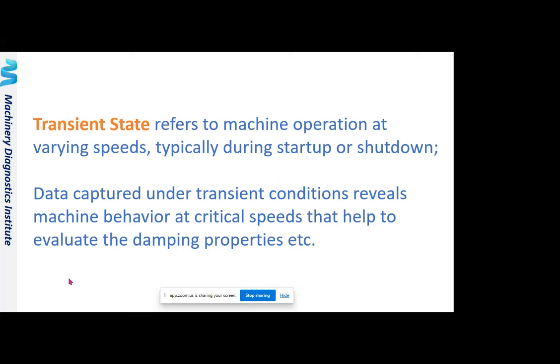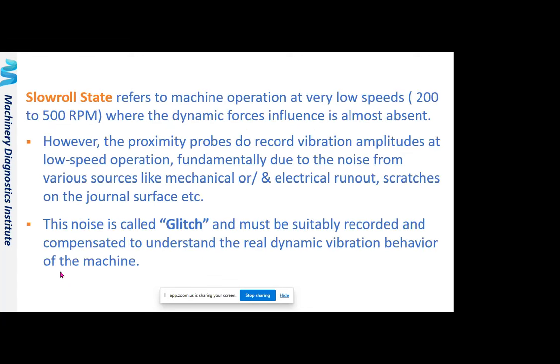Transient state data — captured during startup and shutdown — reveals machine behavior at critical speeds and helps evaluate damping properties. Slow roll data, captured at 200–500 RPM, still records vibration from proximity probes. This signal comes from various sources — mechanical or electrical — such as runouts, scratches, dents, or irregularities on the shaft surface. This is referred to as 'glitch,' which is signal noise that must be recorded and compensated to understand the true dynamic vibration behavior.